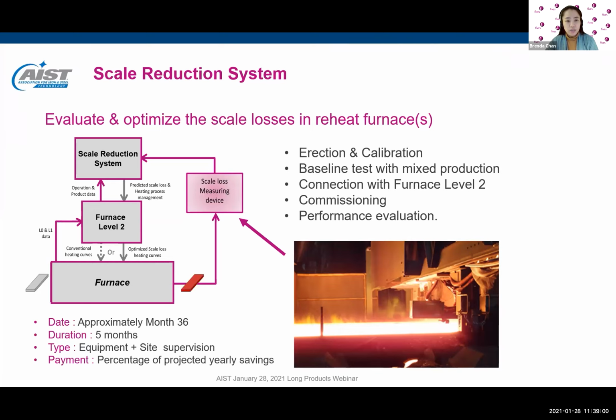So in these steps, what we do with the client on site is the erection and calibration of our measuring system. And then we run the system for several weeks in order to set the baseline test with real and mixed production. After that, we build a special model according to the real data of the furnace, communicate it to the level 2 system, and do the commissioning in order to set all the parameters correctly to get the best performance.